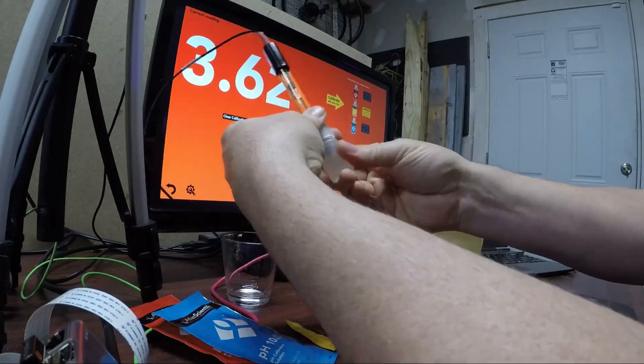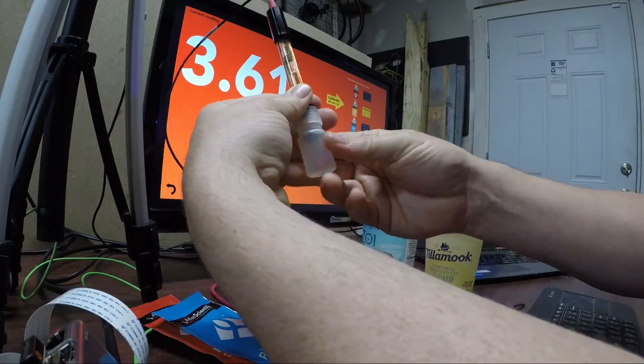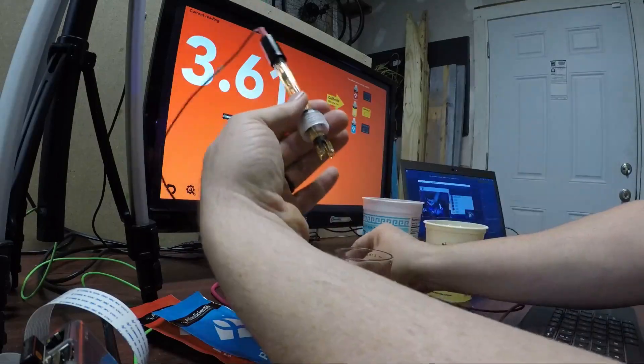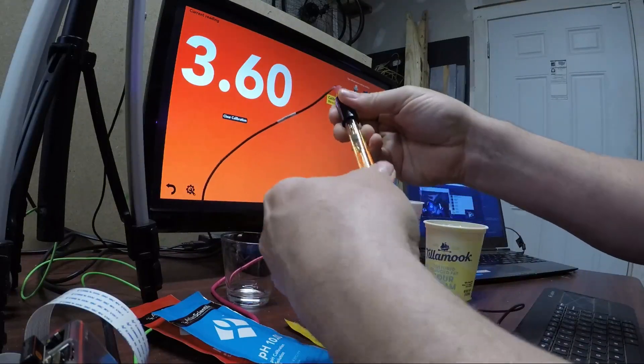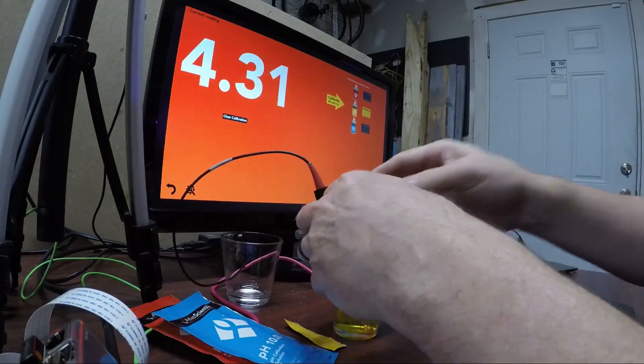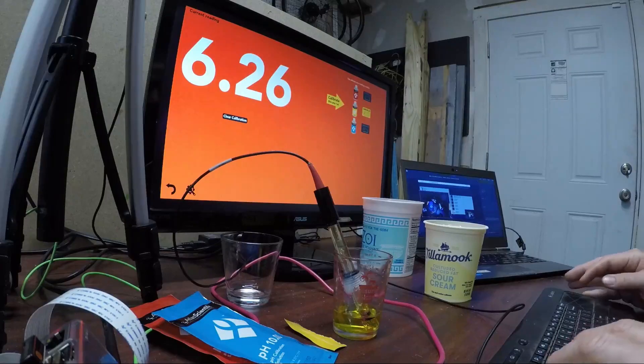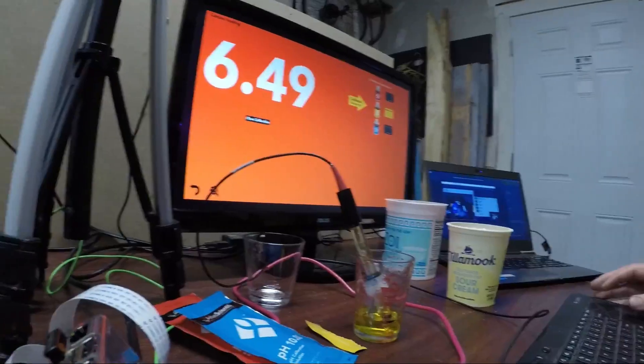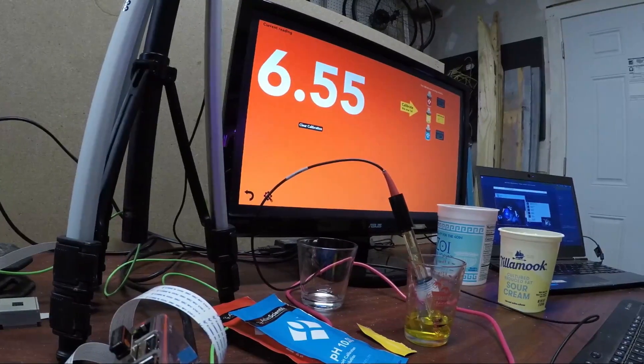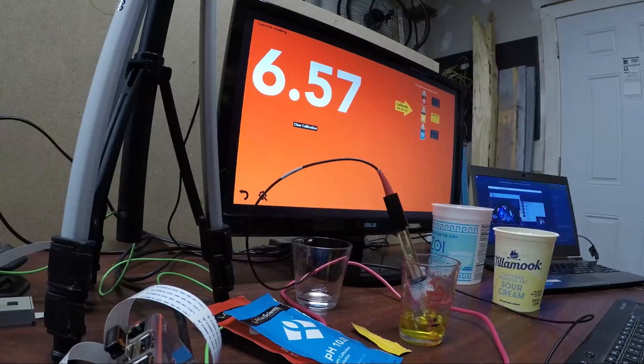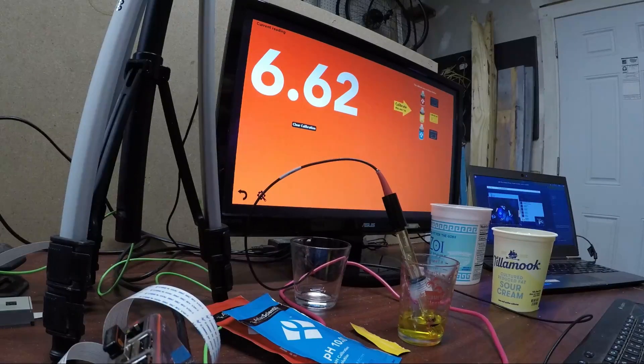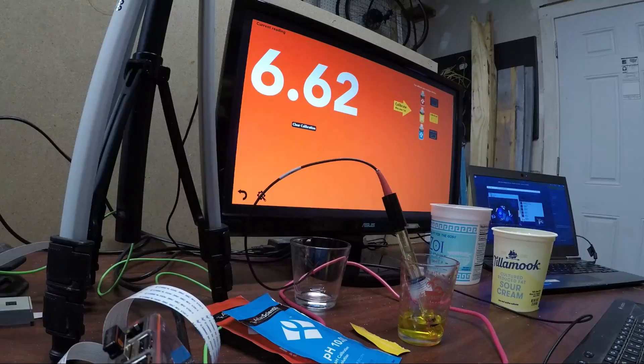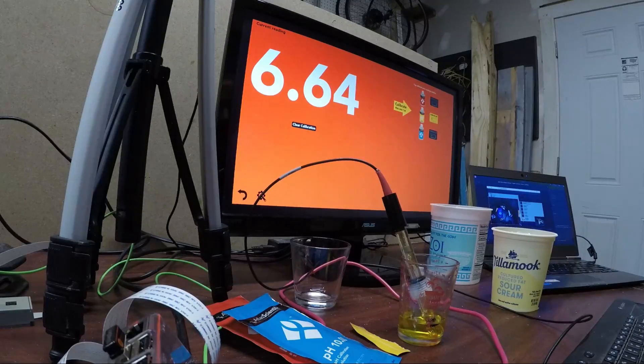The storage solution on the tip here, after you take off the little bottle of storage solution here, you can slide the whole cap and seal off if you want. I'm going to actually leave it on there and just slide it up a little bit. So now we can go ahead and do this. And if we see on our screen here, the calibration, we're going to wait for it to steady out. So they say wait one to two minutes. When it gets a fairly clear reading, then it's settled. You can say that it's not going to bounce around much more.